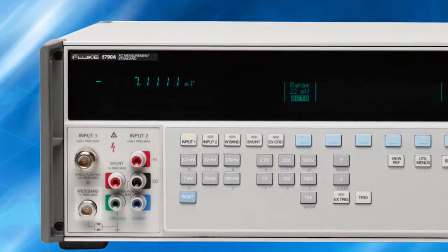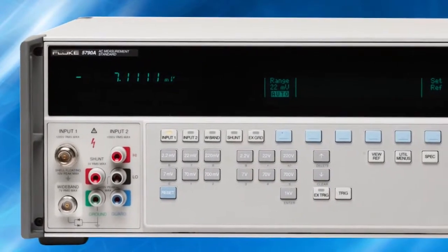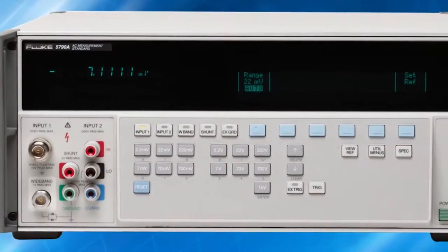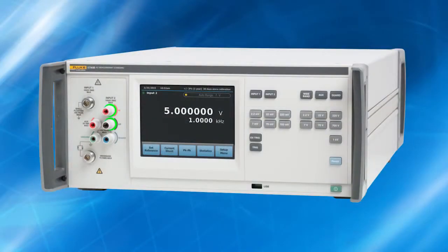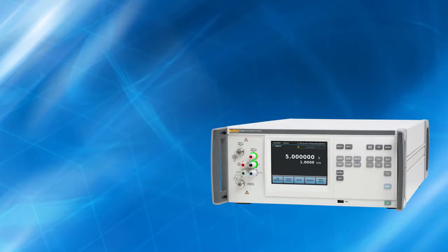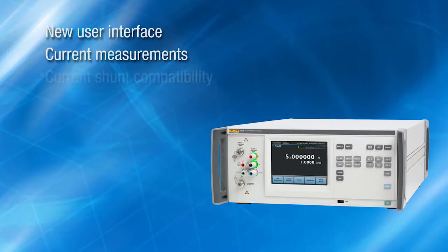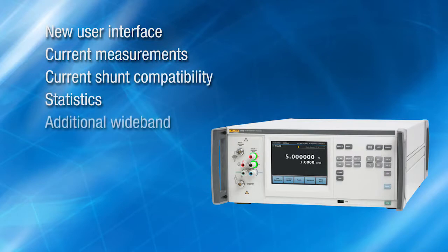Since its release in 1990, the 5790A has been the go-to product for precise AC voltage measurements around the world. The new 5790B has all the features and performance characteristics of the previous 5790A, and we have added 5 important new features: a new user interface, calculation-free absolute current measurements with the Fluke A40B current shunts, statistics, additional wideband, and waveform calculator. We'll talk about each of these.